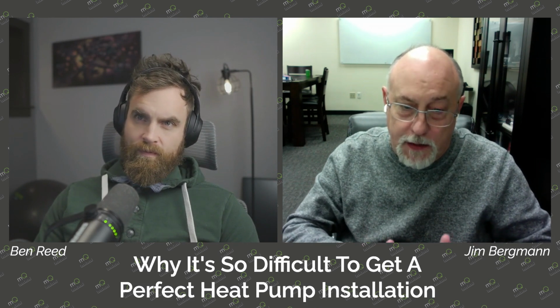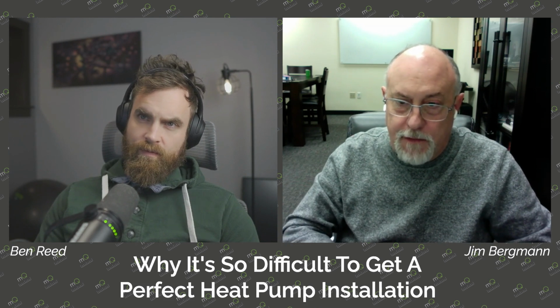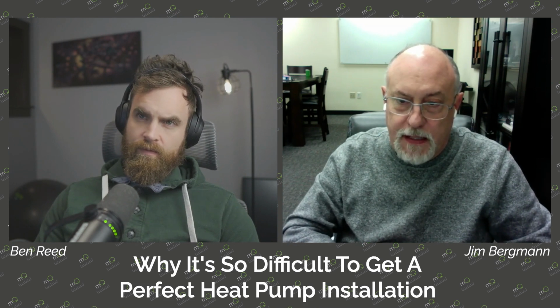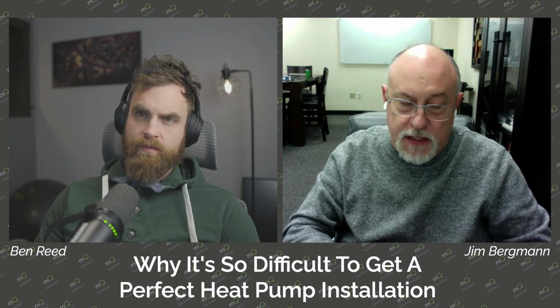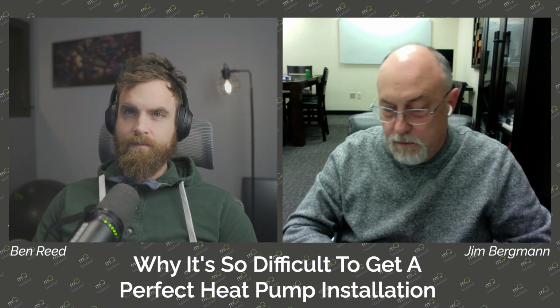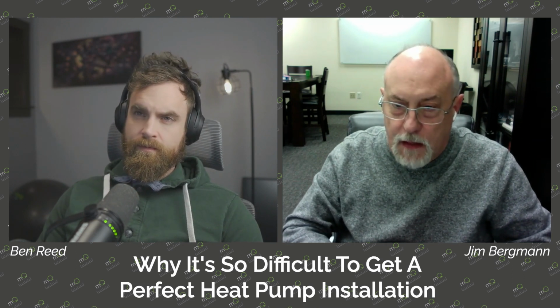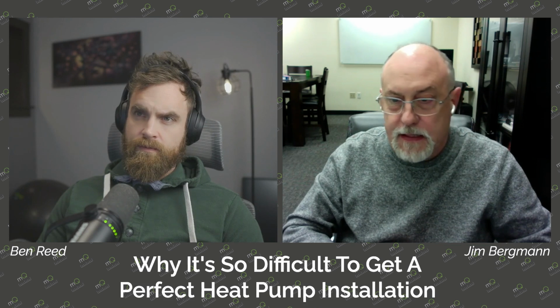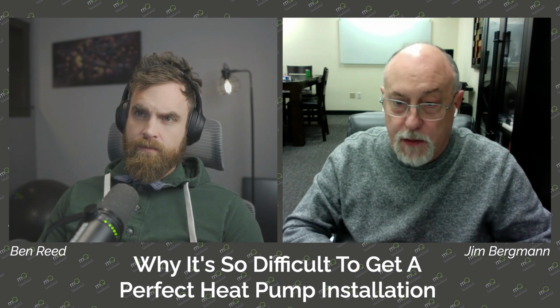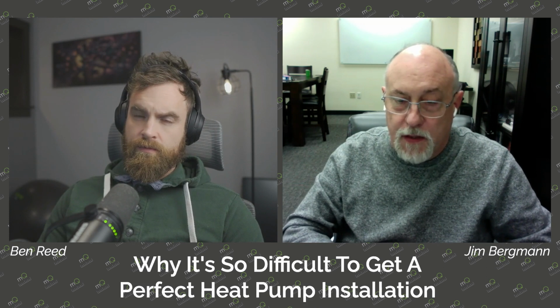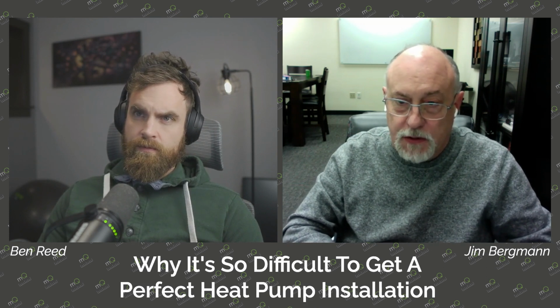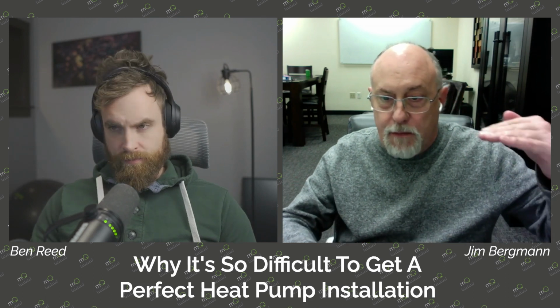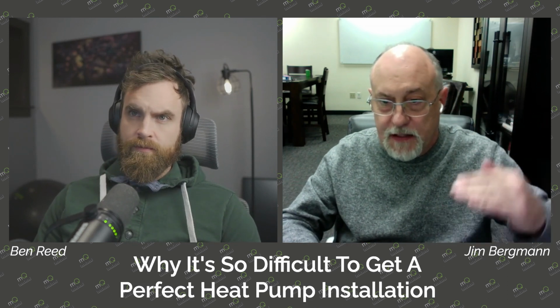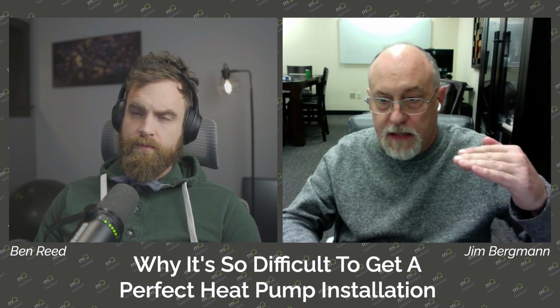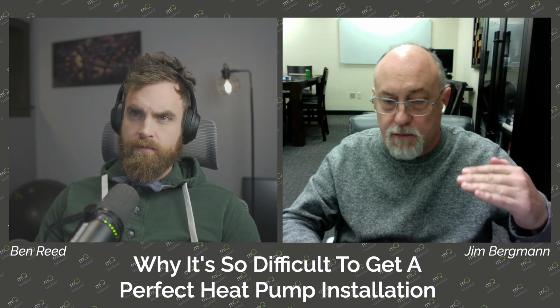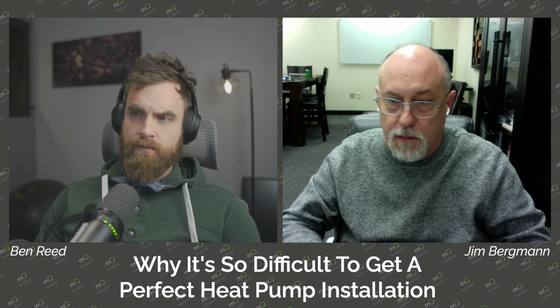So this goes back to, okay, now what do I got to do next? All heat pumps are pretty much bound by physics. So when we put the SEER rating of the heat pump in, we're going to get a certain number of BTUs out. So let's say it's a 60,000 BTU unit. At 0 degrees, it might only be a 52,000 BTU unit, right? And at 70 degrees, it might be a 68,000 BTU output unit. What we really need is for the manufacturers to give extended performance tables so we can go in and say, okay, at what outdoor air temperature, how much capacity am I expecting to see? So that becomes my target. What I'm trying to do is maximize the amount of capacity the heat pump's outputting.